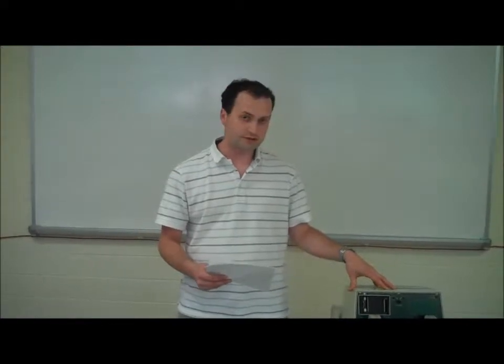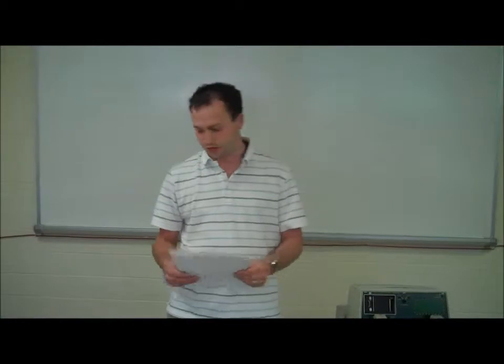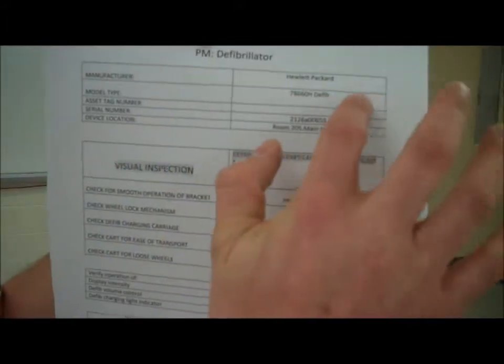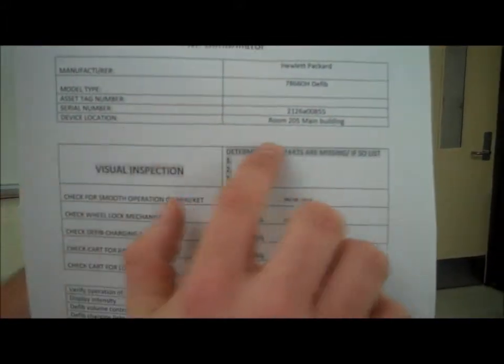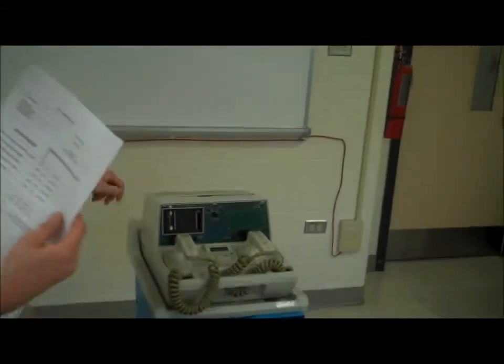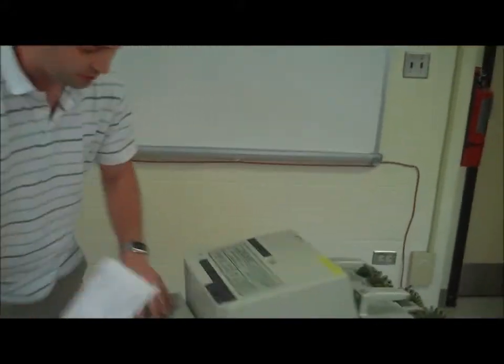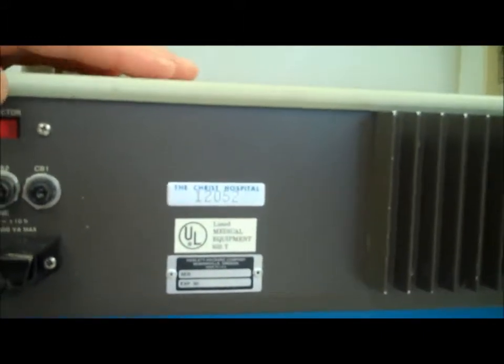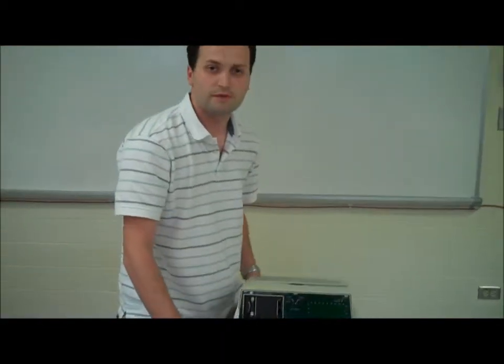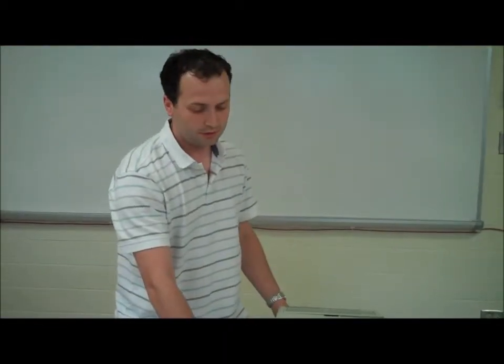So the first step on these devices with your PM sheet, the sheet looks like this. You're going to have a model type. You can put the model number, the Hewlett-Packard. You can get the serial number, which is also usually on the back of any kind of medical equipment, especially on this defibrillator, which is down here. You want to make sure you have that for your documentation. And always have a date when the PM was performed. So you want to have some kind of a label that you can stick on this defibrillator.